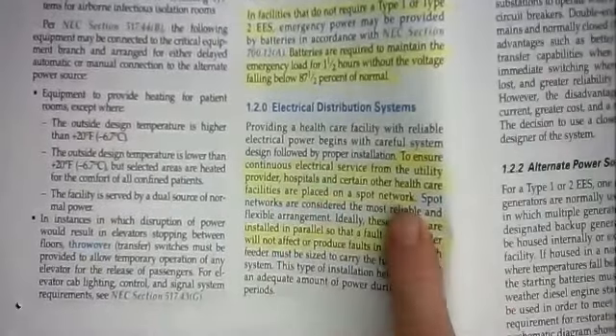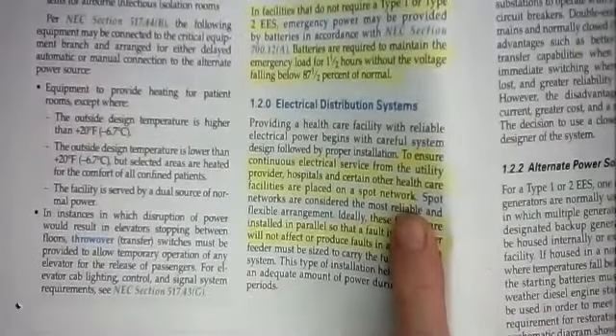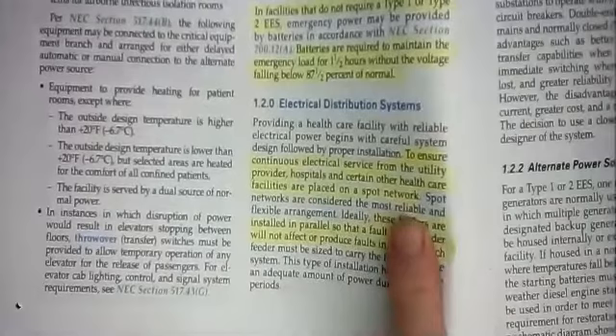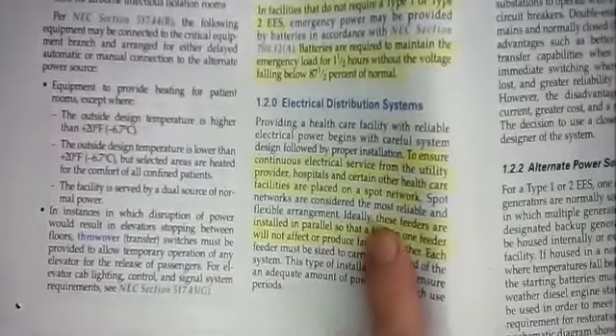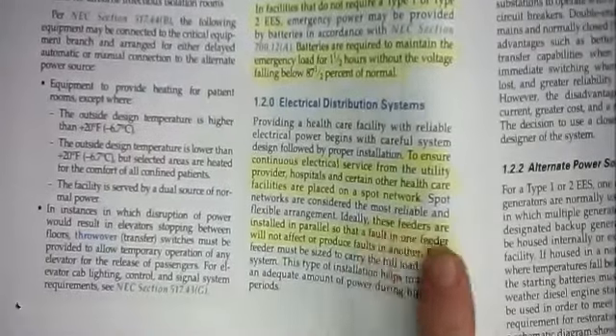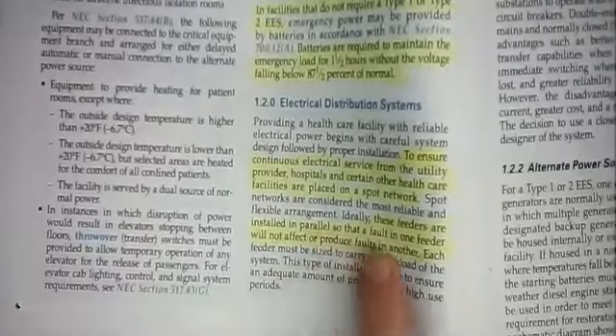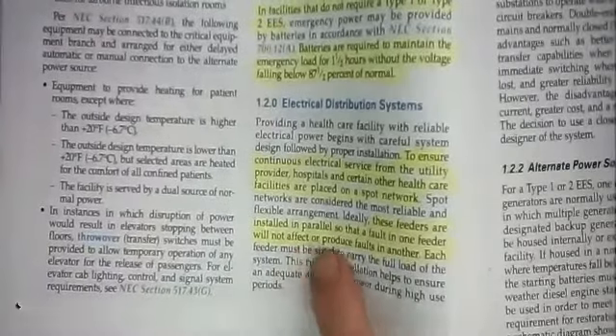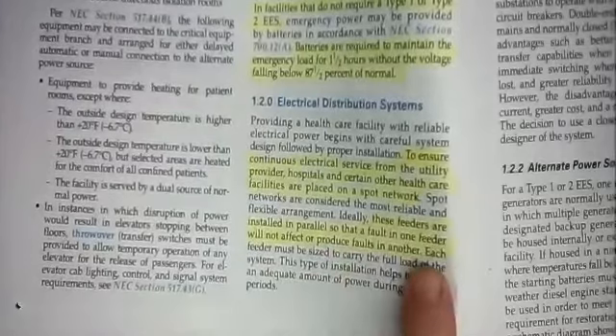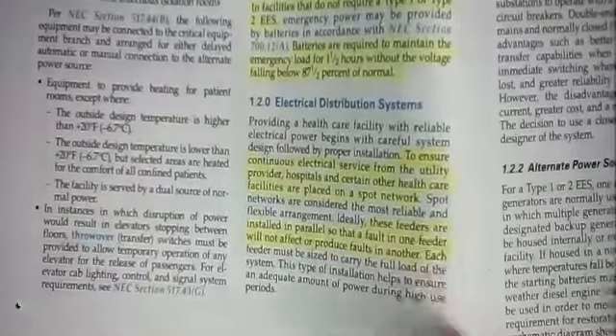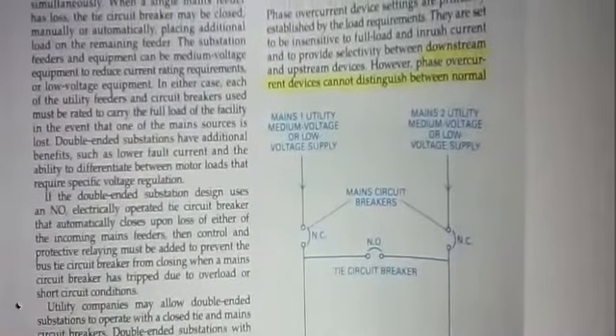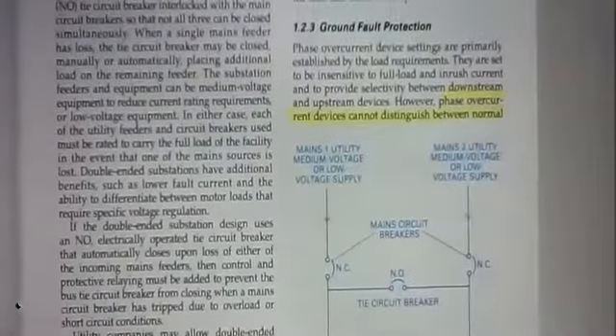Hospitals and certain other healthcare facilities are placed on a spot network. We used to call this a redundant network. Now they call it a spot network. We'll see why it was called redundant, and we'll see why it's called spot now. These feeders are installed in parallel so that a fault in one feeder will not affect or produce faults in the other. So over on page 7, there's a drawing here. Figure 3 shows us a spot network.